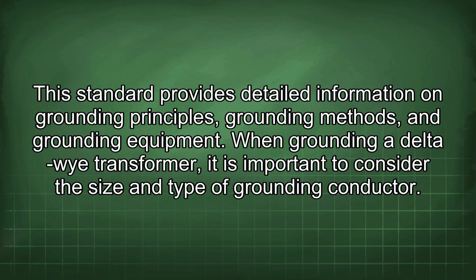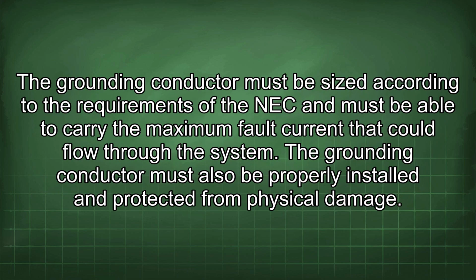When grounding a delta-wye transformer, it is important to consider the size and type of grounding conductor. The grounding conductor must be sized according to the requirements of the NEC and must be able to carry the maximum fault current that could flow through the system. The grounding conductor must also be properly installed and protected from physical damage.